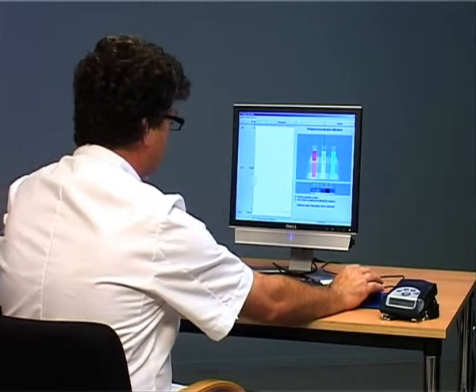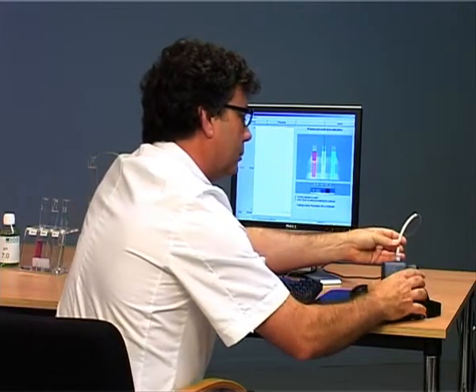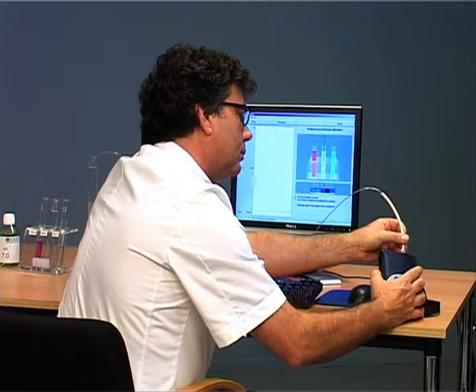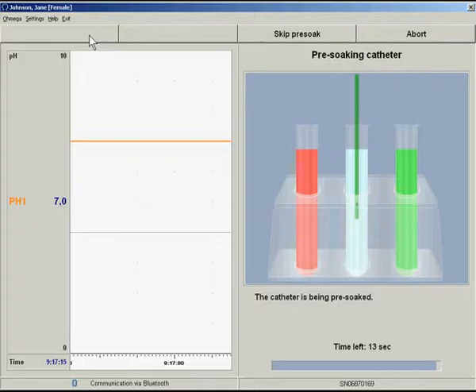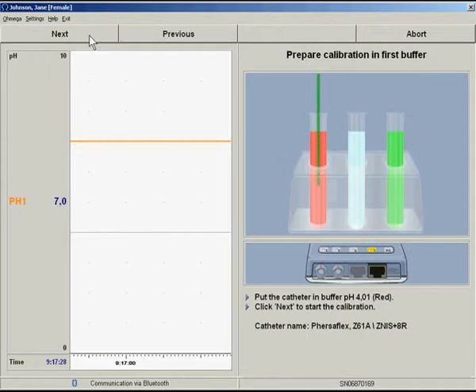Connect the impedance pH catheter to the Ohmega recorder. You are now ready for pH calibration. Some types of catheters need to pre-soak before calibration can be done. Therefore, place the tip of the catheter in the calibration tube with water. MMS's Virtual Instructor Program, VIP, will guide you through the calibration procedure.